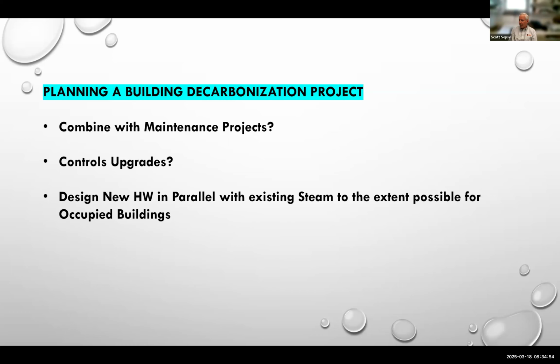You may also want to upgrade your controls. You may need to add sensors and programming to aid in control and commissioning of new systems. As an example of this, we added thermostats in a dorm room that we had done setback testing on, where we previously had only run the building system with single sensors for different exposures of facades. There was really no feedback into the BAS system for individual rooms. Now the upgraded system will quickly respond to problems at specific locations and alert us to problems room by room rather than by exposure level. The final product is better comfort for the occupants and better diagnosis for future maintenance problems.